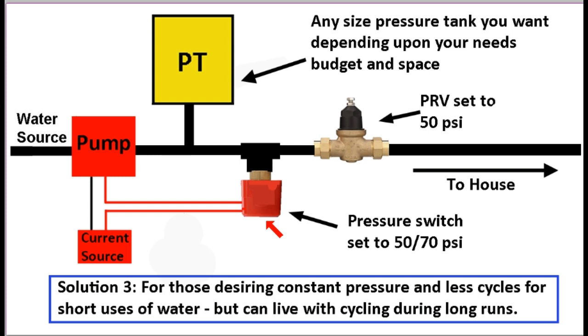Okay, what you do is you have a pressure reducing valve. Let's say you want your pressure set to 50 psi. Okay, now what you do is you set your pressure switch to 50 to 70. So the tank will never go below 50. The tank will go from 50 to 70. Now, as you use water, the pump will go on and off, filling the tank to 70 and then reducing to 50 before it goes off. Meanwhile, since the tank is never below 50 pounds, it cycles from 50 to 70, this pressure reducing valve on the output will limit the output to 50 psi, and you will get a constant pressure of 50 psi all the time.